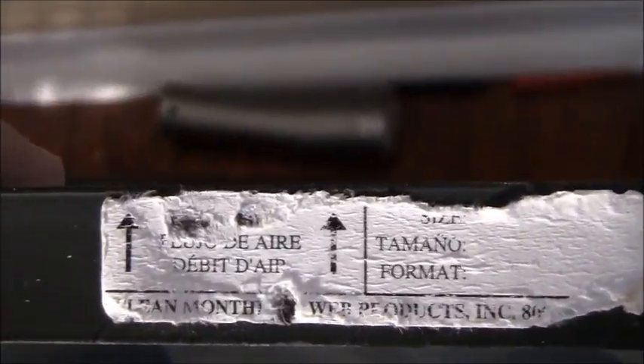Now, how good of a filter does this do? I think it does a pretty good job. When I wash it out, you can see a lot of the lint and debris caught inside here, but they probably have better filters today. This one was already here. Let's see if there's a sticker on it. There's a sticker right here, and it's almost to the point where you can't read it. It just tells you the direction of airflow. I don't think it's directional, and the airflow doesn't matter whether it goes one way or the other. You can swap these around. But in any regard, this is the air filter that I have, and they want the air to go up this way. So let me go ahead and put that in.